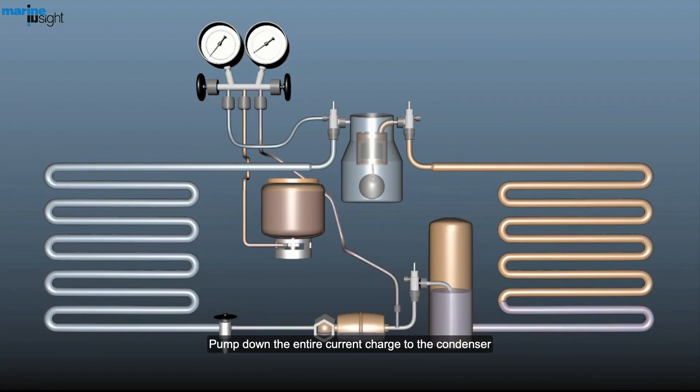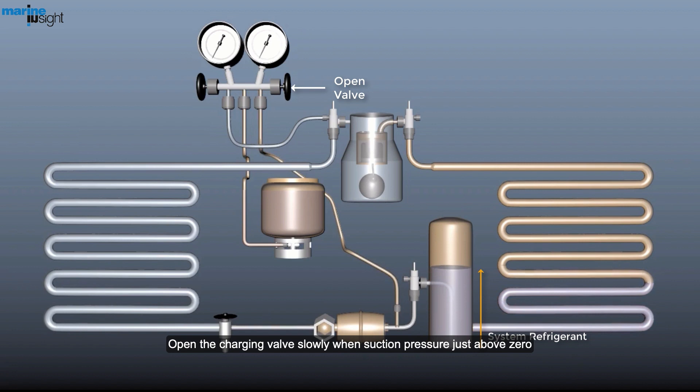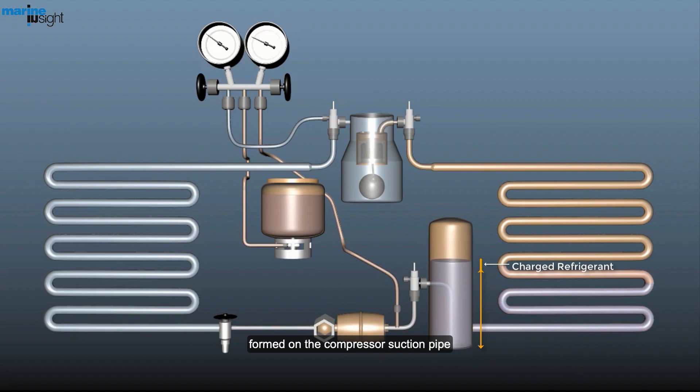Pump down the entire current charge to the condenser. Open the charging valve slowly when suction pressure is just above zero. Valve opening should be done slowly so that no frost forms on the compressor suction pipe.